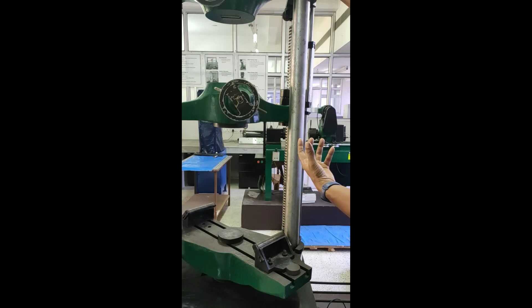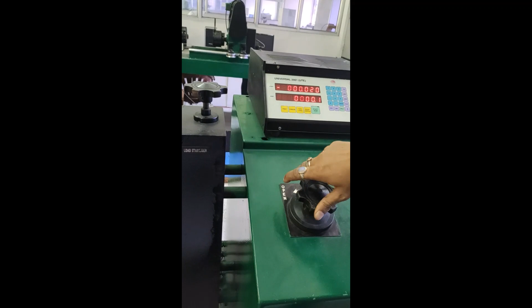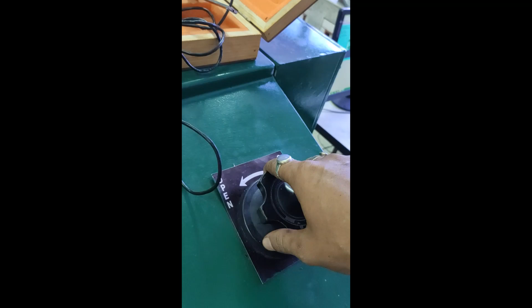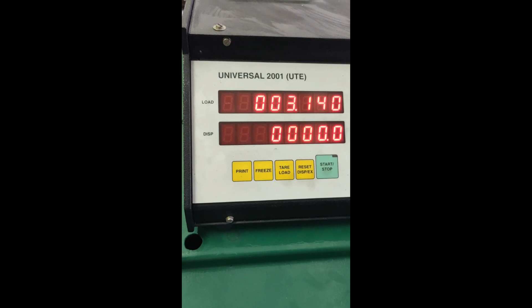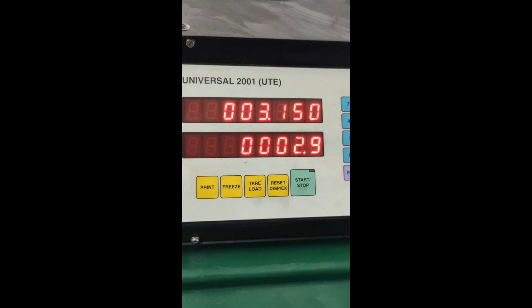Floating is what? We have to close this valve. This portion has some dead weight. That dead weight needs to be lifted by hydraulic pressure. So that is called floating. For doing this floating work, we need to initially close this valve during the testing. Close this valve, then start the hydraulic here, press this hydraulic button, and then open this valve. Once you open this valve, you should see at least 1 or 2 mm displacement, the piston should move upward. That means the whole fixtures are floating on the hydraulic oil.